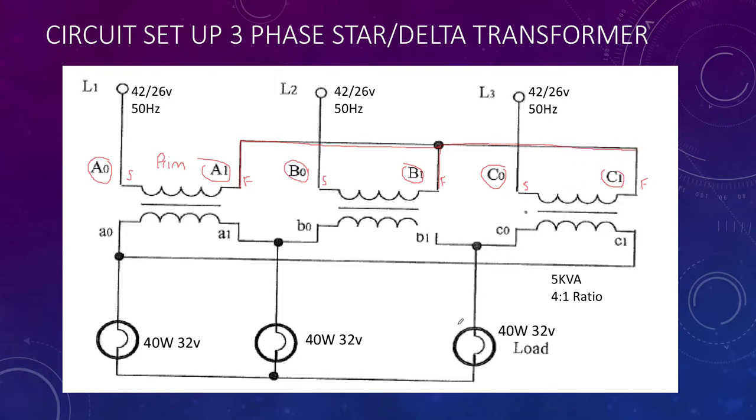Again, very important to get start to finishes correct. In this particular case, all the finishes have been connected together to create a star point. As long as the load going out the other side is balanced, you won't need to take that star point back to the neutral on your supply. Then we have our three supplies, line one onto A phase at 42 volts. So that takes care of the primary side of the transformer, and our primary is connected as a star.